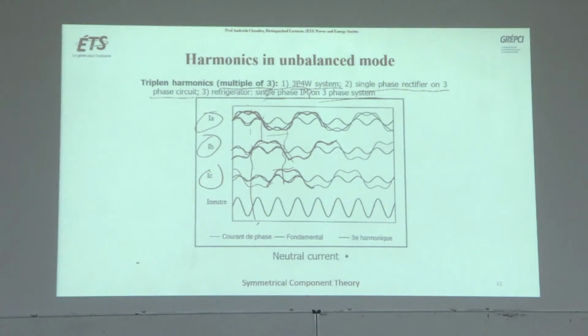But the third harmonic of phase A, third harmonic of phase B, and third harmonic of phase C are in the same phase, same amplitude. So when they come to neutral, if currents IA, IB, IC are balanced, 120 degrees apart, the sum will be 0. But if their third harmonics are coming to the neutral, they are the same magnitude and also in the same phase. So you will have the sum of IA3, IB3, IC3, and in the neutral you may have very high current.